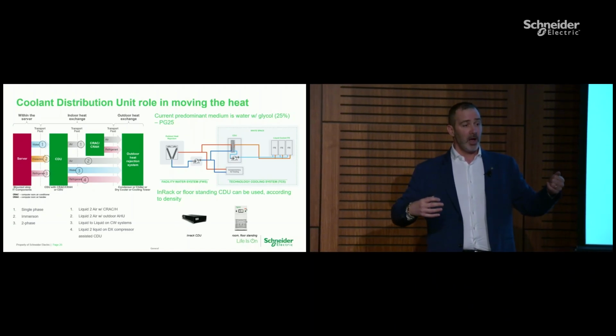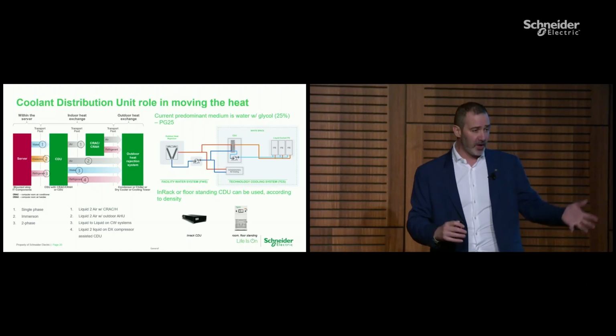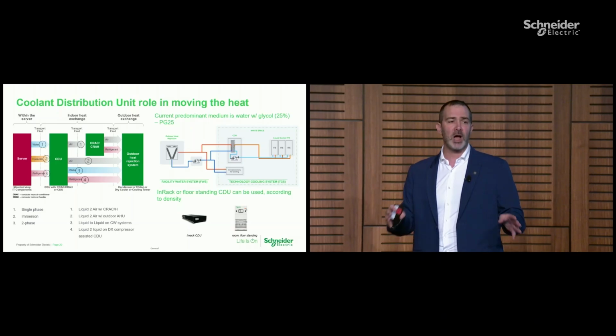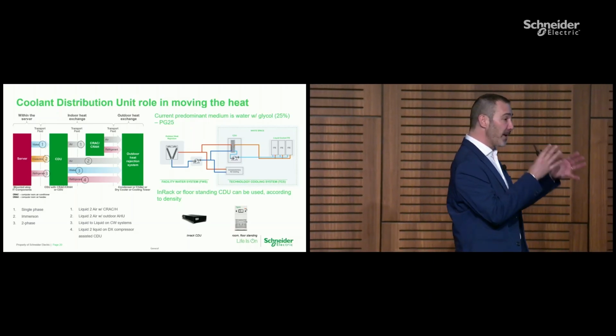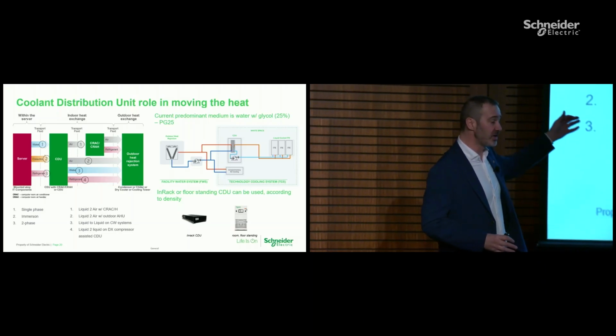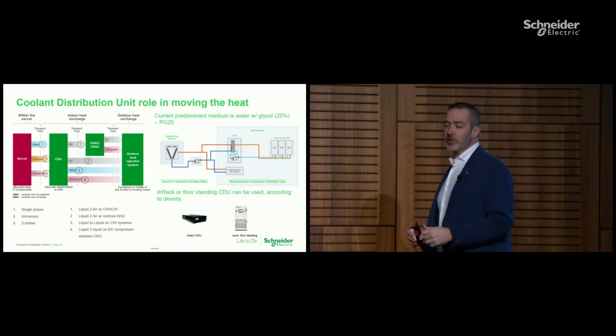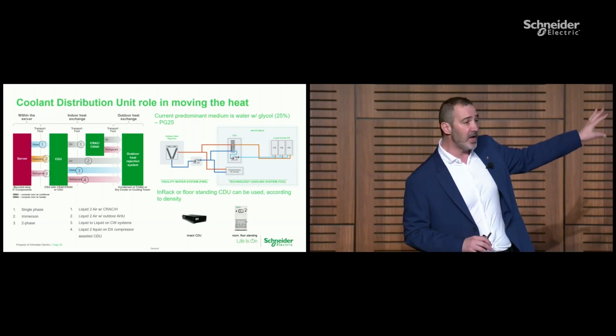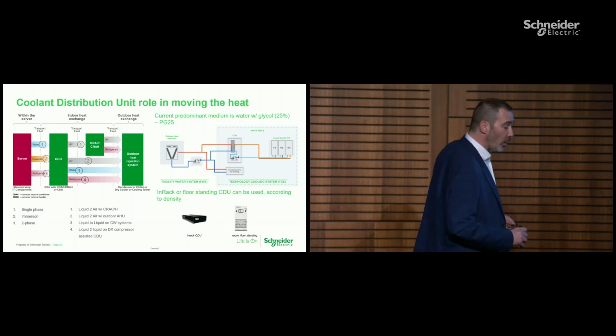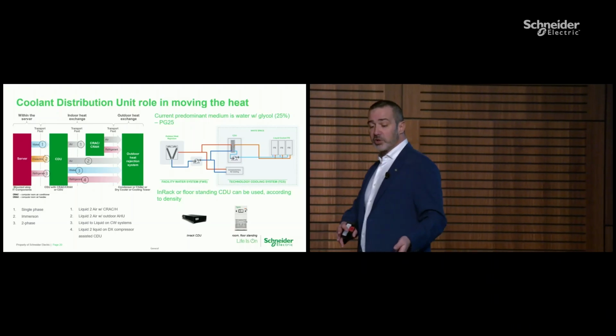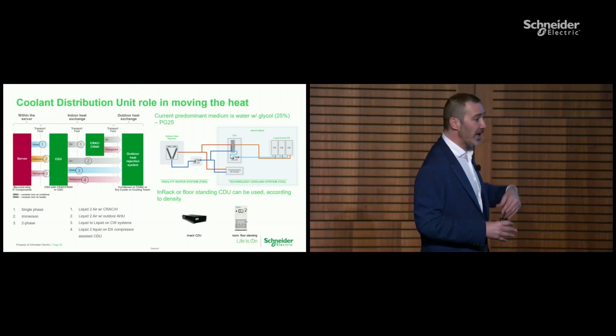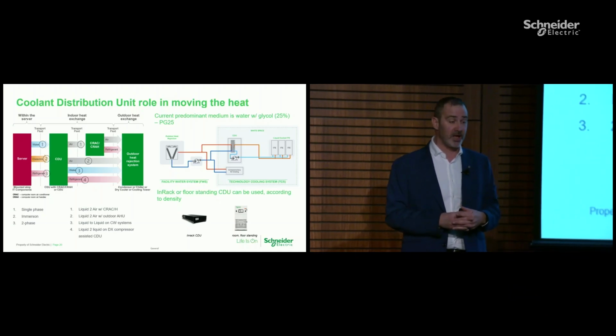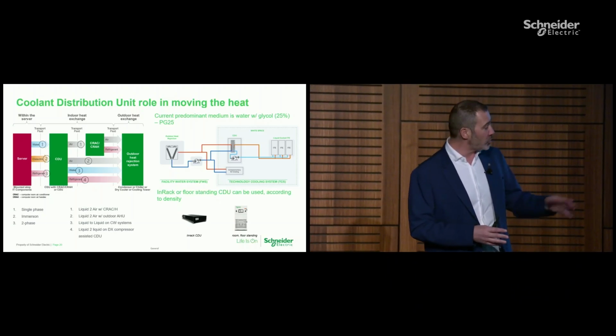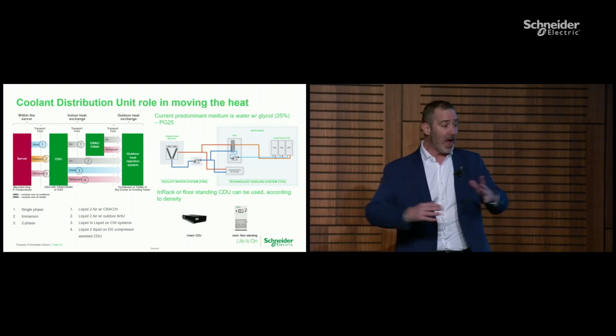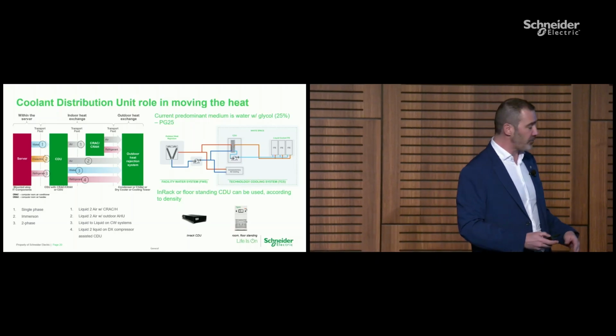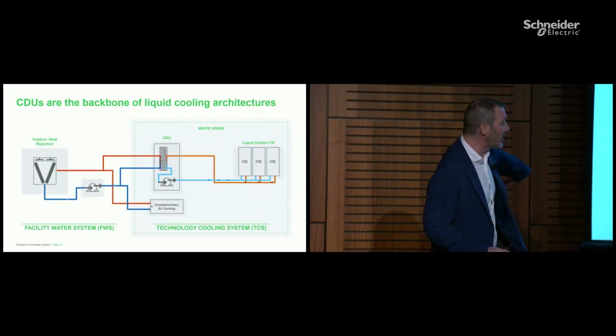You can do this with air and liquid, with liquid and refrigerant, with refrigerant and water, with water and water. All of those are CDUs, all of those. The primary application today is liquid to liquid, water and water. So something like the picture on the top right, where you have a heat rejection unit which moves the water on the facility side, and the CDU which moves the water into the server. Then this can be floor standing or in the rack. If you were at the cooling booth earlier, you saw that both solutions, in the rack or floor standing, are CDUs. And the main purpose of these CDUs is essentially to divide the facility water and the technology water.